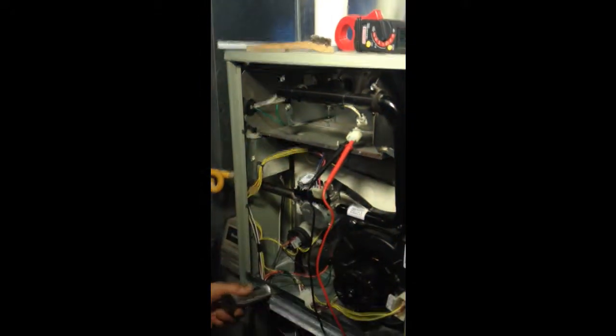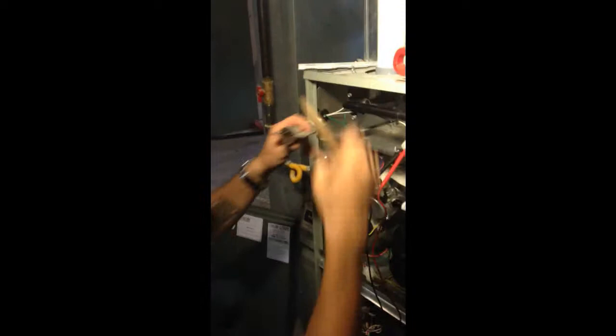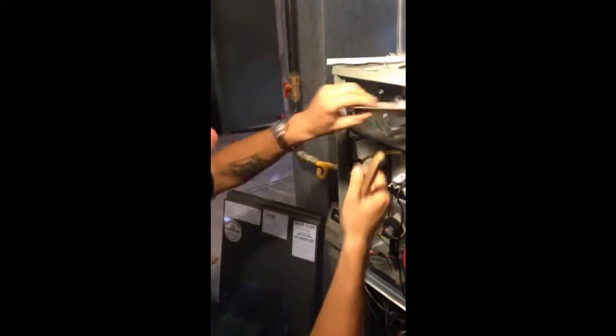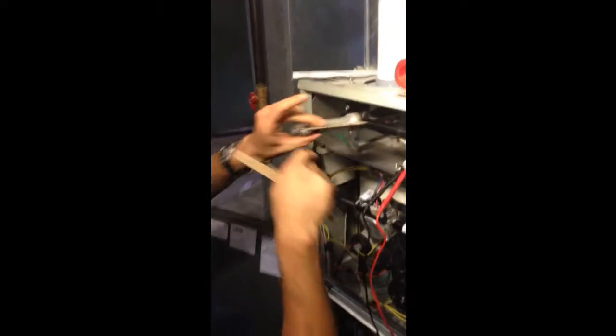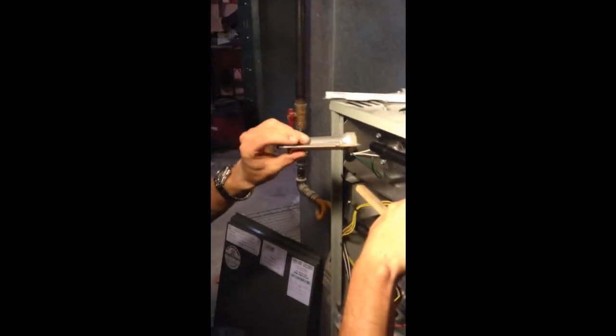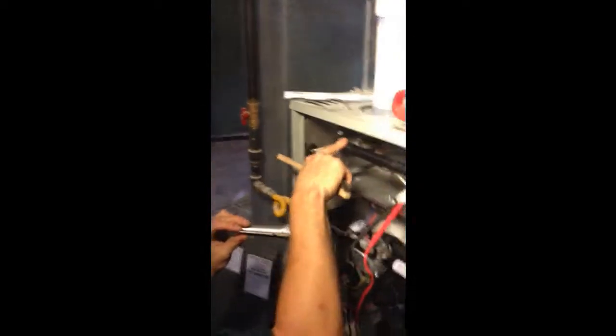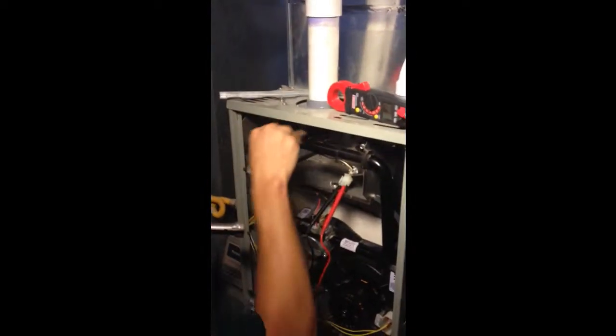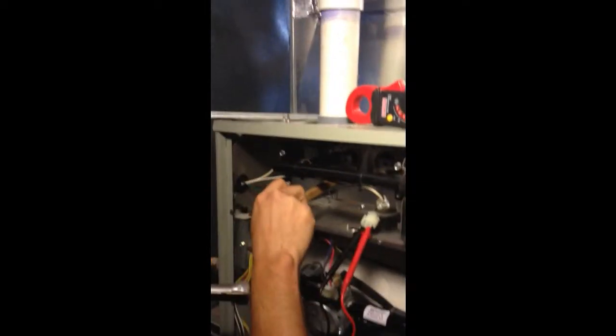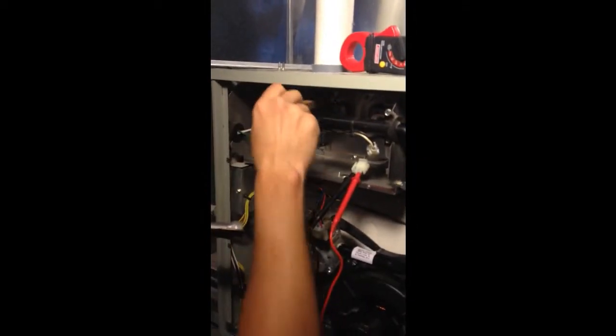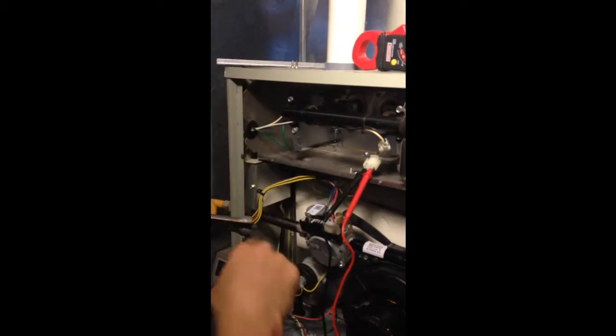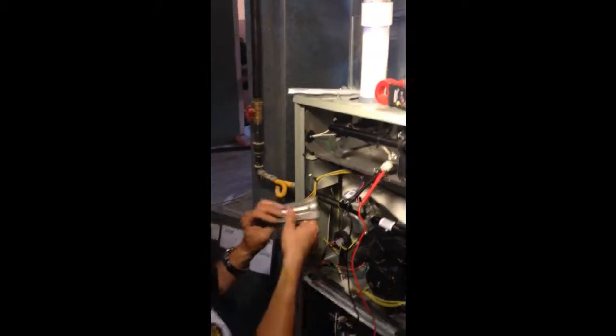So as part of the maintenance, first we'll get to this. I pull each individual burner out, and they sit in there like this, and the gas shoots through here. The fire starts on the igniter side and jumps over all three. And then on the left side here's a flame rod, which I'm also going to pull out and clean. That senses that the flame made it all the way across, and it tells the circuit board, hey, we got fire in all three spots. You can go ahead and start the blower.